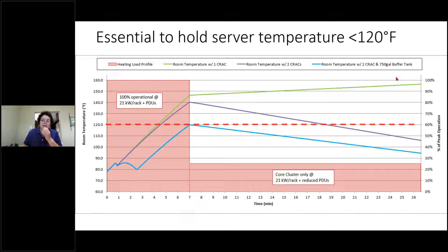So the client said, well, I'll just keep the CRACs in there just in case, because we could always open up the doors and get a little bit of air movement going, as well as pumping the in-row coils with this pre-reserved 750 gallons of chill water. It was a lot of conversations to get to the bottom of that.